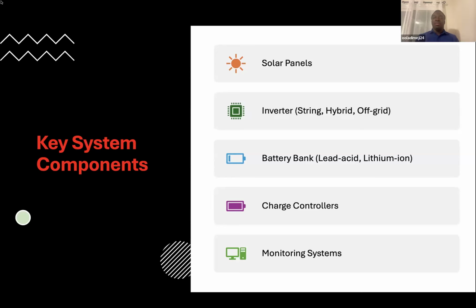You have the input to the system, then you have the outputs from the system. For example, the solar panel: if a solar panel is not functioning well, you want to see that as a system. There are inputs that are expected to go into the solar panel for it to generate the output. So the input here, you are talking about the solar panel being exposed to enough sunlight, and the total surface area of the solar panel being well covered and well exposed. Then from the output, based on the specification of the solar panel, you know from your measurements what the output is supposed to give you. So that's the basic and fundamental way to troubleshoot a system.